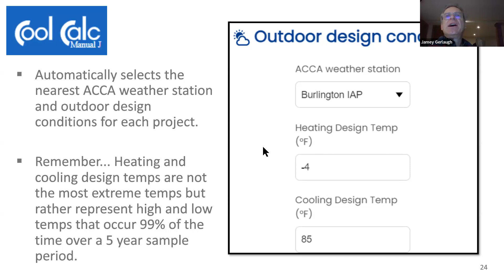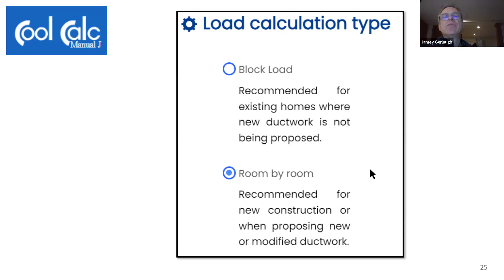There are two different types of load calculation. There's a block load, which is basically the heat load for the whole house, and then there's a room by room calculation type. Block loads are recommended for existing homes where new ductwork is not being proposed. Room by room is recommended for new construction or when proposing new or modified ductwork.